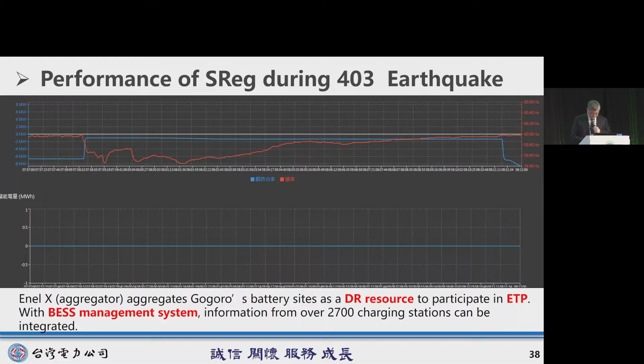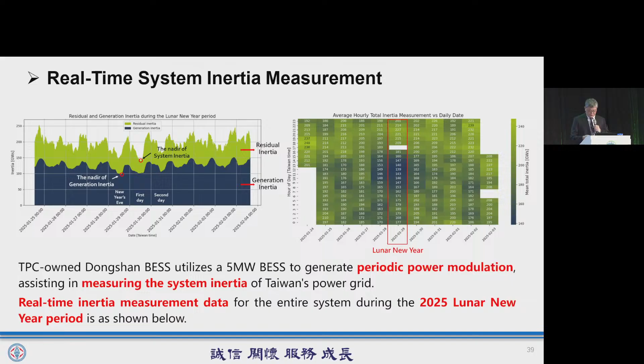Real-time system inertia measurement: here's an example of how we use BESS to better understand system conditions. During the 2025 Chinese New Year vacation, Taipower used a 5 megawatt BESS at the Dongsan substation to measure real-time system inertia. We found that on January 29th, inertia dropped to just 137.68 gigawatt-seconds, a clear sign of how low inertia can get during holidays. This data helps us plan stability strategies for future low-inertia scenarios.